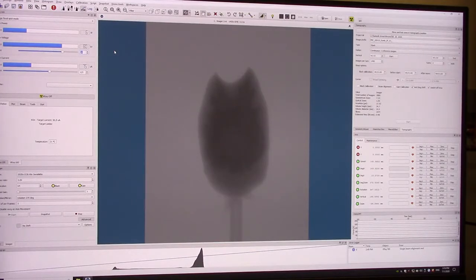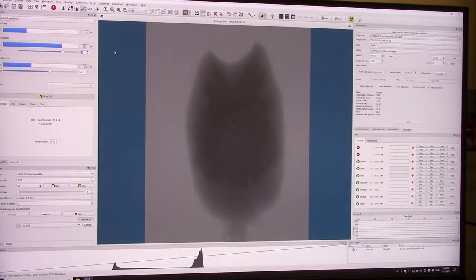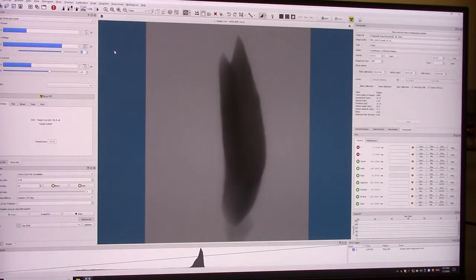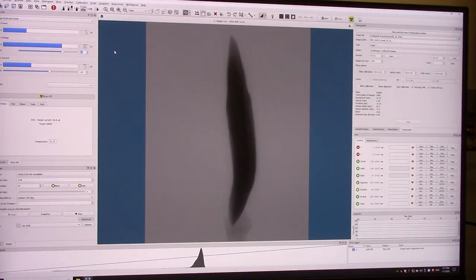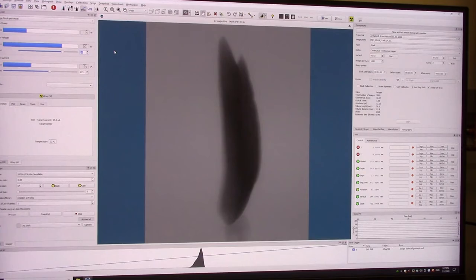So, as you set this up, you're going to want to typically try to get your sample to fill the screen as much as possible. Again, be careful not to run your sample into the X-ray tube. And then you can also recheck your sample to see how sort of centered it is, if you wanted to, by putting it on rotation and spinning it around, which you should do anyways, because you want to make sure that histogram is okay for the full 360 degrees of your sample.